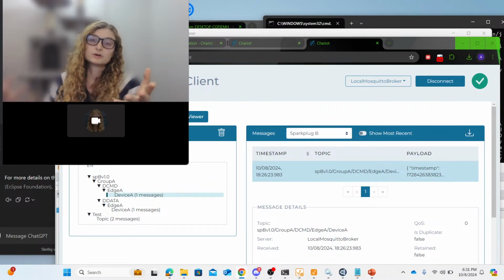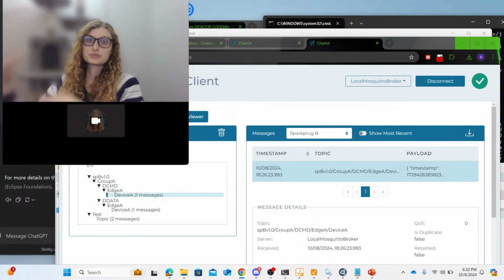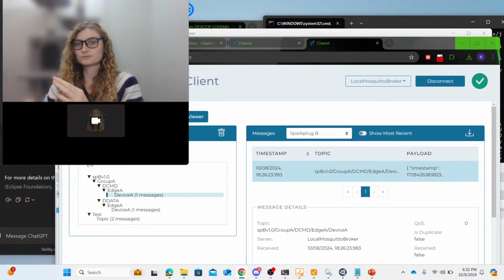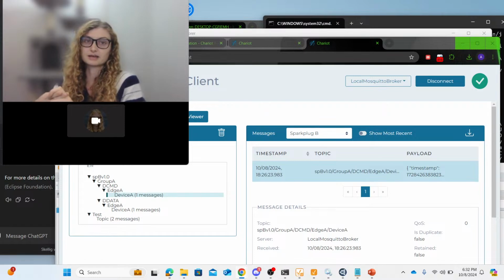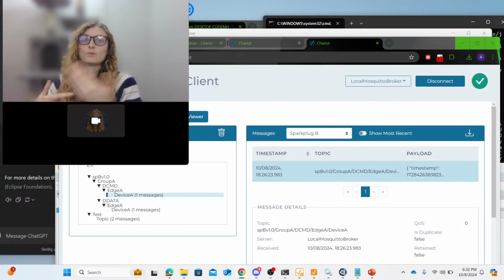But maybe one use case is you want to send down all of these set points, like we just showed 2 minutes ago, through MQTT. Well, you could do that through SparkPlug, because Ignition first uses SparkPlug, and second, you're going to know for a fact if that bioreactor is online. Through Ignition's UI of whatever HMI you make, if it hasn't gone red or stale, or you didn't get an alarm, you will know that those parameters actually made it there.